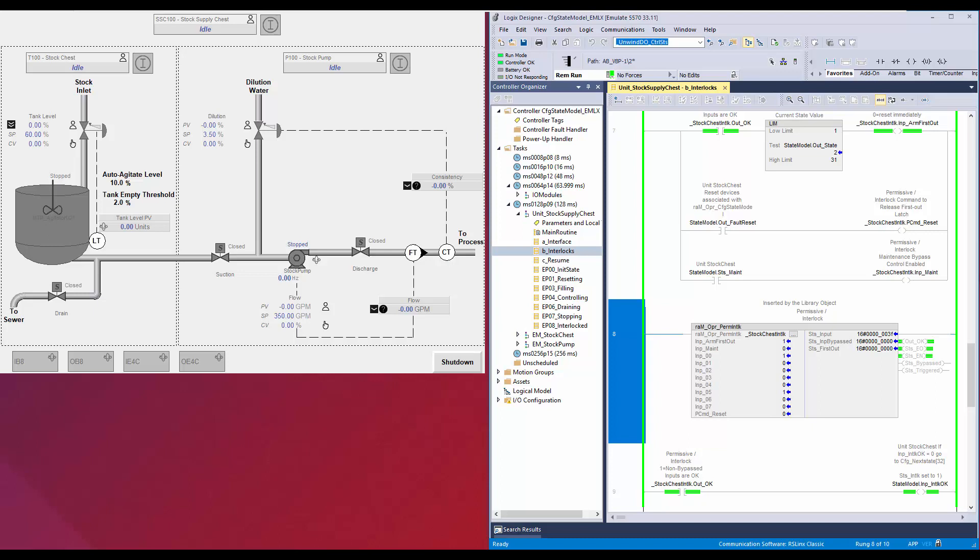The instruction can monitor up to 32 inputs. Each input's OK state is configurable as ON or OFF. The inputs can be bypassed during maintenance operation. First OUT capture is used to identify the first input that failed its OK condition.